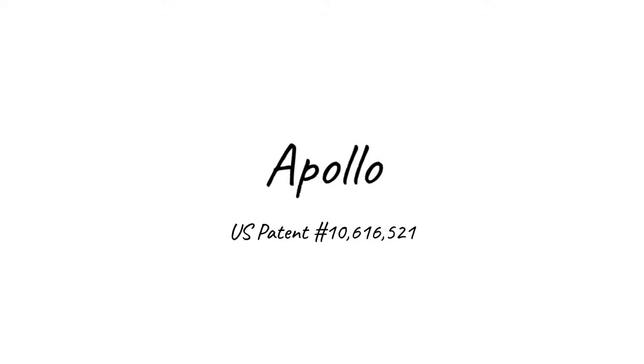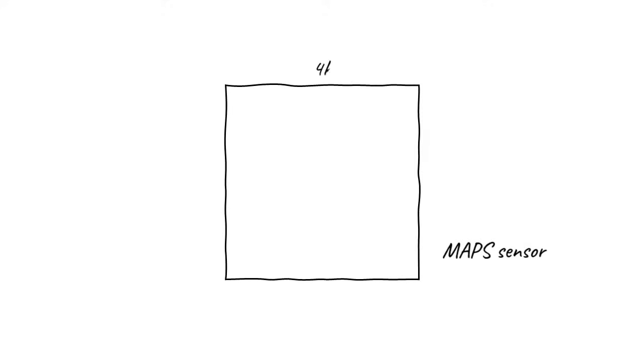Here's how it works. We start with a CMOS MAPS sensor, with 4096 by 4096 pixels. At the highest level, this looks similar at first to previous generation direct detection sensors. Similar pixel size, in this case 8 microns. Similar number of electronic components in each pixel. Similar radiation hardening.